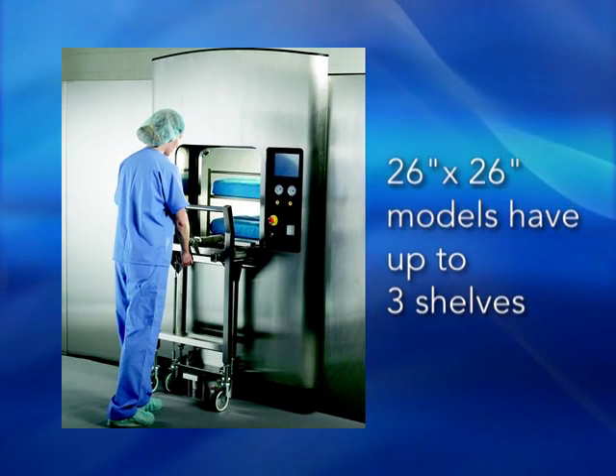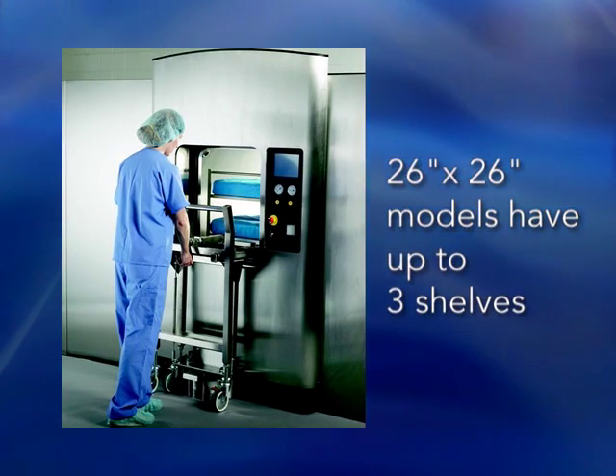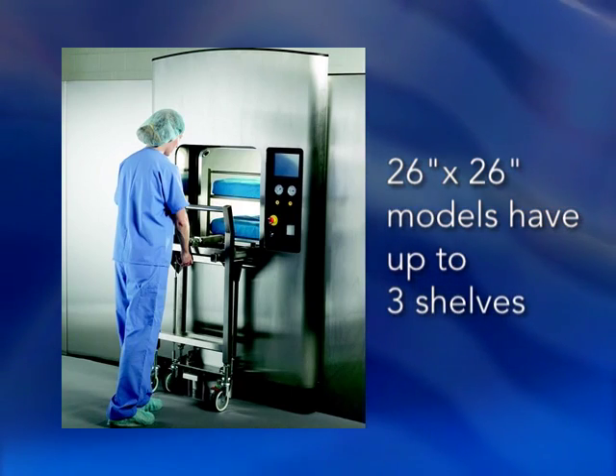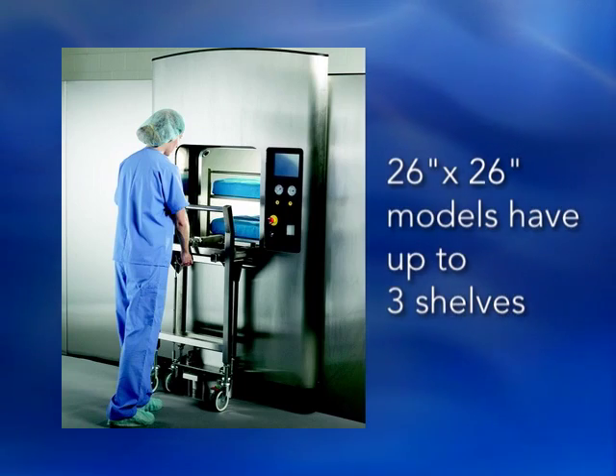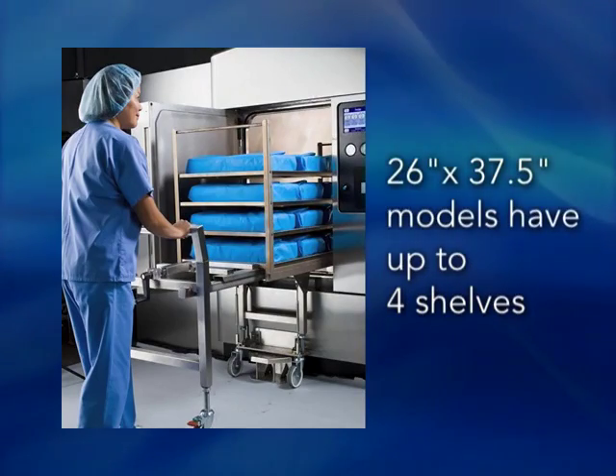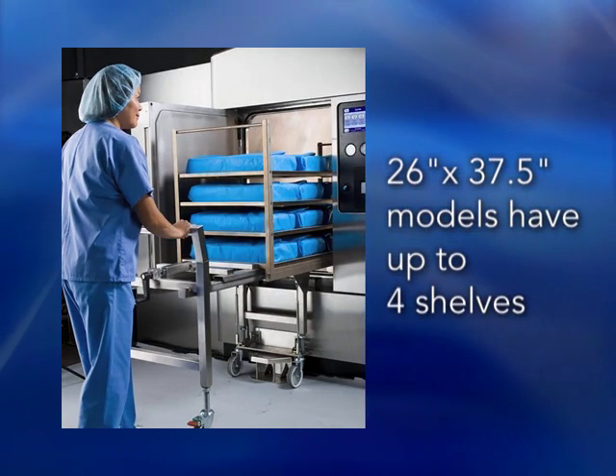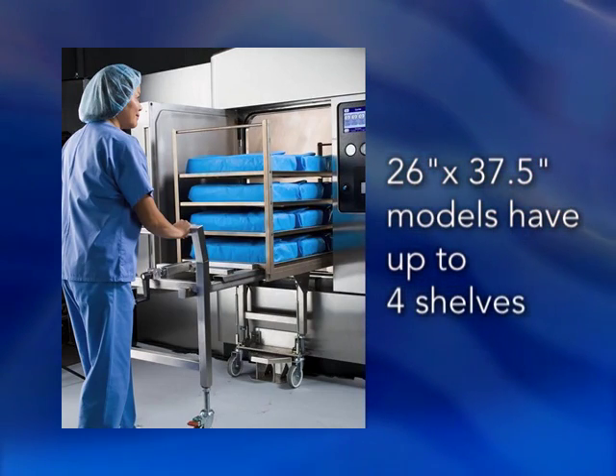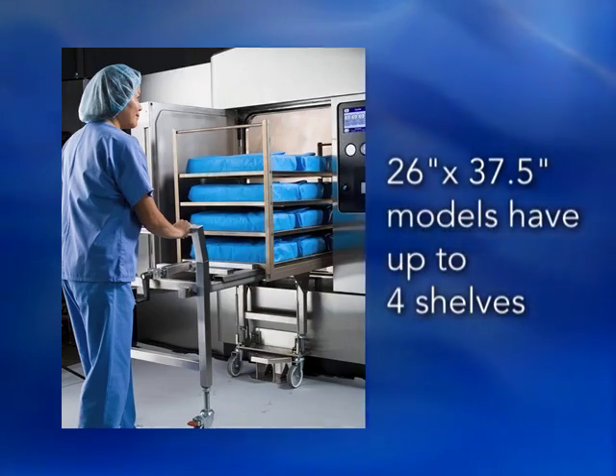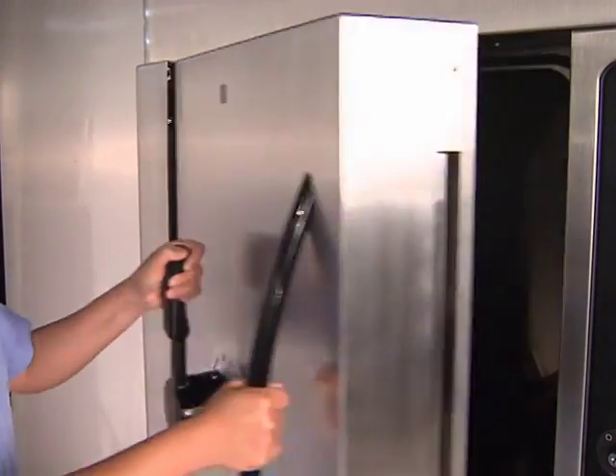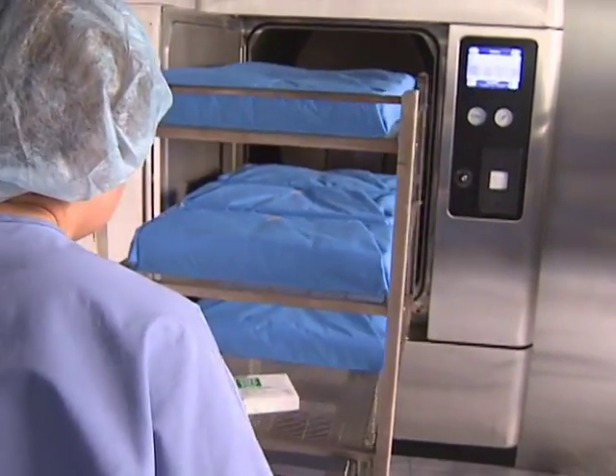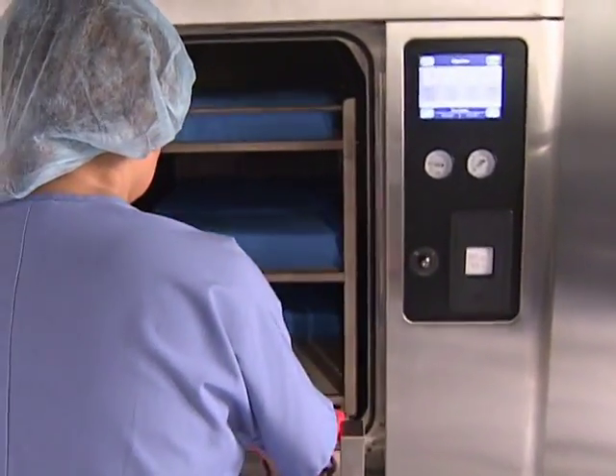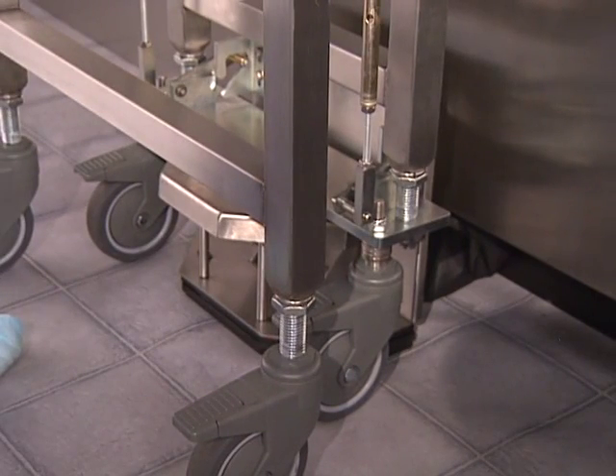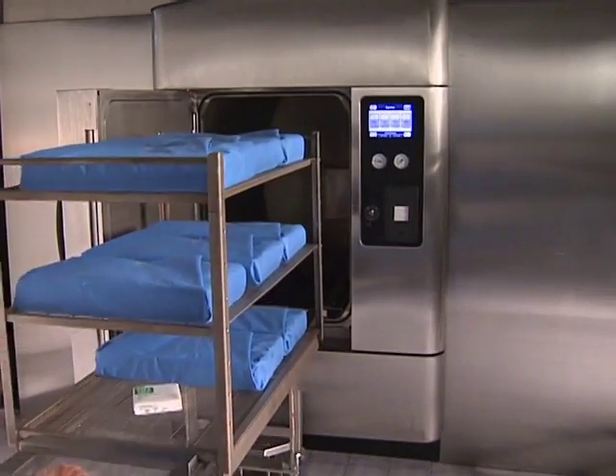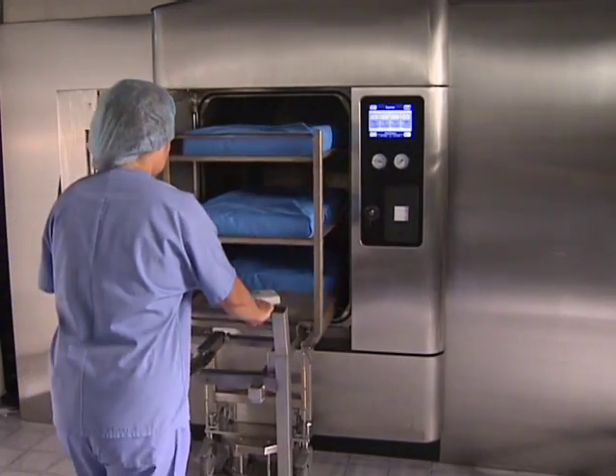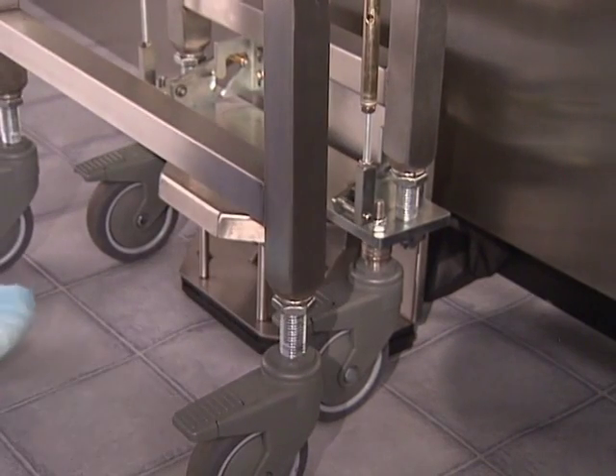The 26-inch by 26-inch sterilizer loading cars feature 2 or 3 shelves, 1 or 2 height-adjustable removable upper shelves, and 1 fixed-height lower shelf. The 26-inch by 37.5-inch sterilizer loading cars feature up to 4 shelves, 2 or 3 height-adjustable removable upper shelves, and then 1 fixed-height lower shelf. To load the chamber, first open the sterilizer door. Maintain a line of sight with the chamber opening and roll the transfer carriage forward until the latches connect with the dock mounted to the floor. It is not necessary to look down at the dock. The dock guides the transfer carriage into proper alignment with the sterilizer and secures the transfer carriage to the chamber.